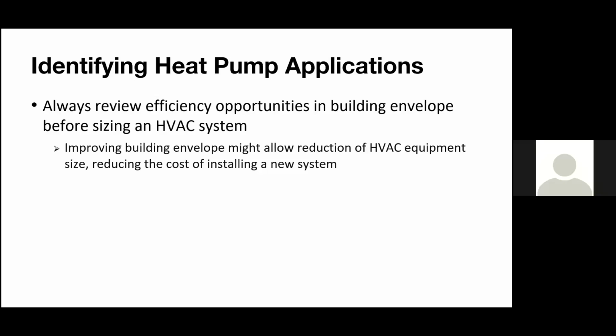So those steps are going to kind of go in order, but it's really important when you're sizing your heat pump systems to make sure that you're not doing any last minute changes to your building envelope, because that does change and that does affect the system. And you want your heat pump system to be sized correctly, or all those efficiency terms that we're talking about, you might be chasing a little bit more, you might not be getting.